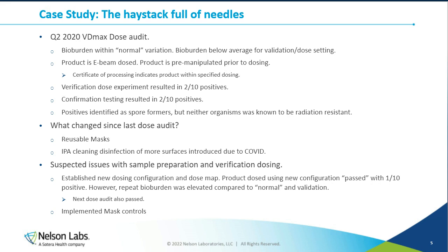So when we did the dose audit, as an example, the bioburden was within normal variation. So it was bioburden that they were used to seeing, and it was actually even below the average that was used to set the dose. The product's E-beam sterilized, so it is exposed to E-beam dosing. In order to aid with that, it was pre-manipulated product, so the product was sent to the laboratory, cut up, and then repackaged prior to dosing to facilitate proper dosing. So the certificate of processing for that dosing didn't show any issues. It showed that the dosing was within specification.